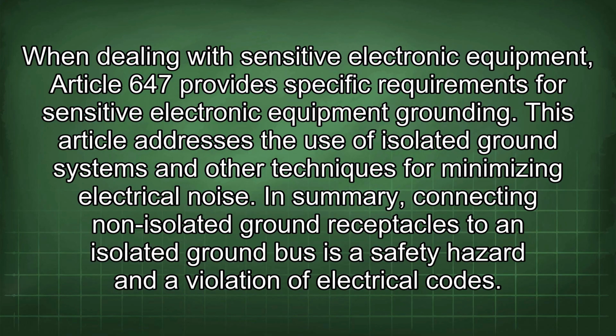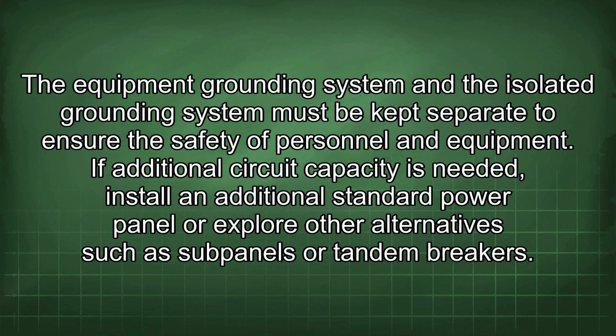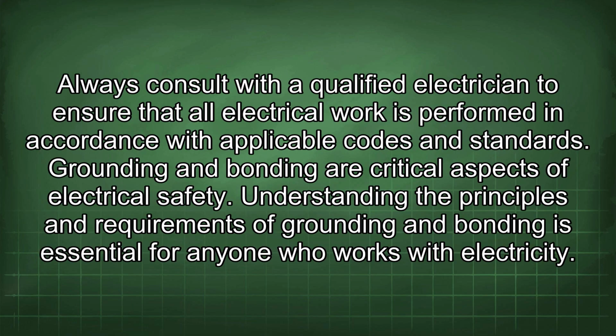In summary, connecting non-isolated ground receptacles to an isolated ground bus is a safety hazard and a violation of electrical codes. The equipment grounding system and the isolated grounding system must be kept separate to ensure the safety of personnel and equipment. If additional circuit capacity is needed, install an additional standard power panel or explore other alternatives such as subpanels or tandem breakers. Always consult with a qualified electrician to ensure that all electrical work is performed in accordance with applicable codes and standards.